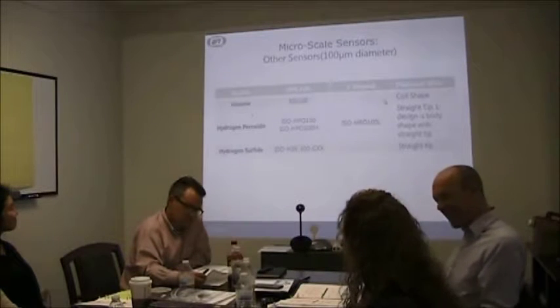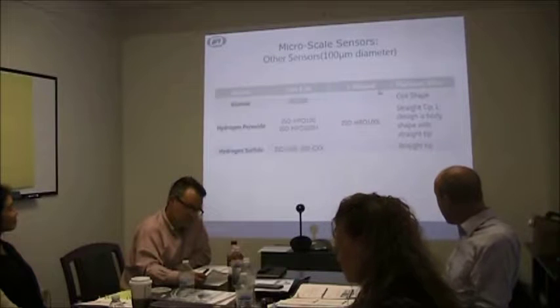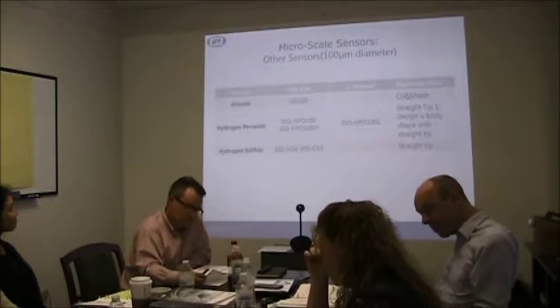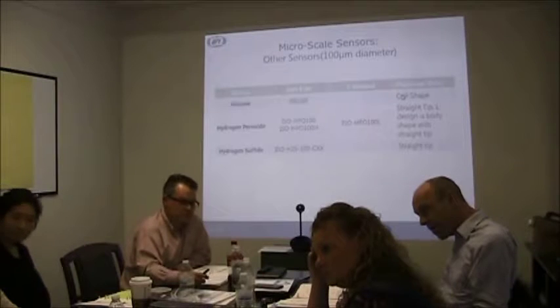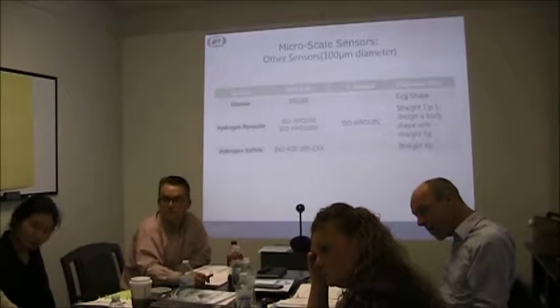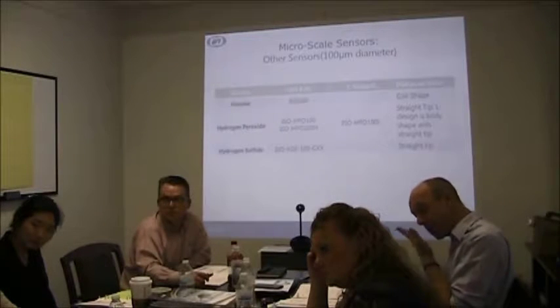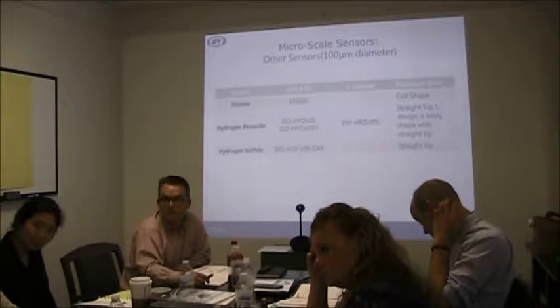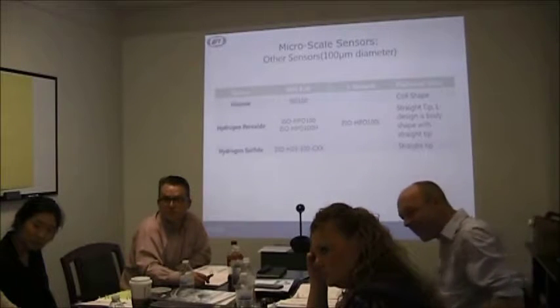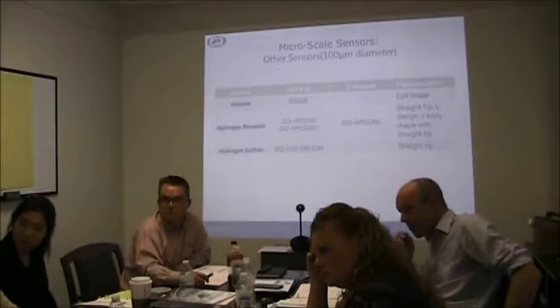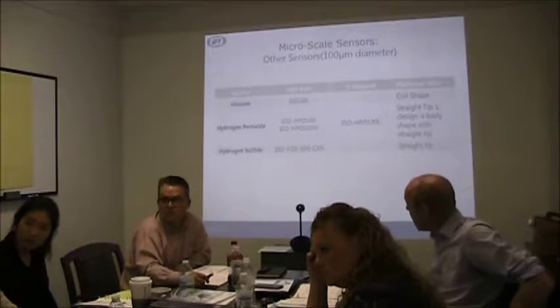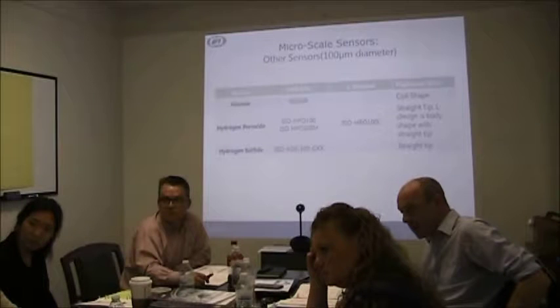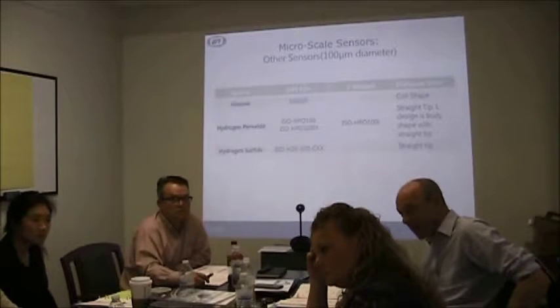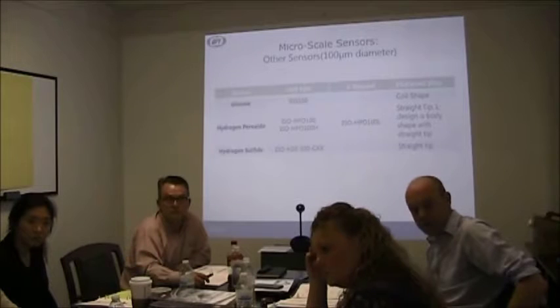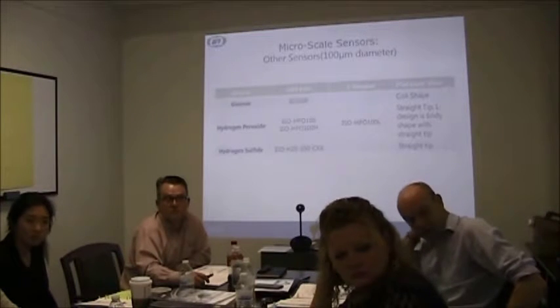What's so important about that? Well, for the glucose sensor to detect the concentrations it can and to last as long as it can, the platinum wire has to be shaped in a coil so that it can be infused with a membrane enzyme on a piece of cotton. So I'm going to take a piece of cotton? No, it's already built like that. You don't have to do anything with it. You can use it as is. It's just the fabrication of the design. It's an enzyme reservoir.